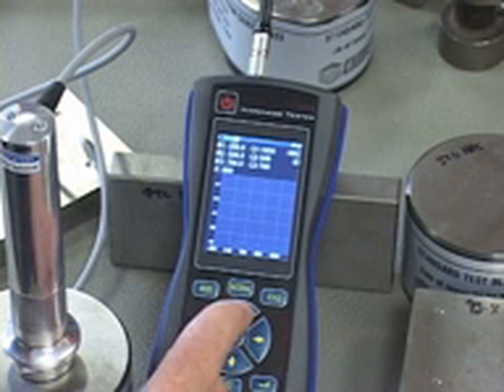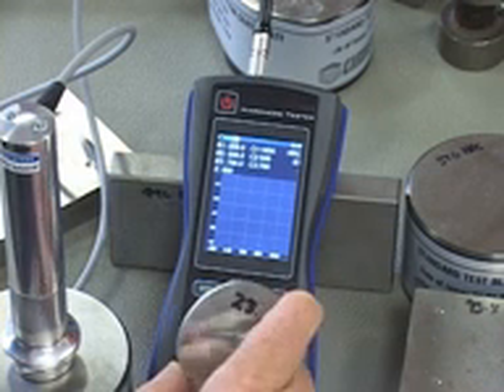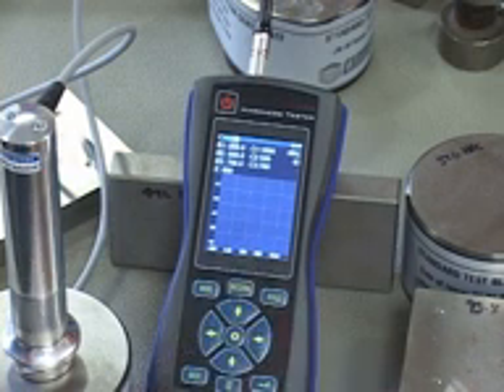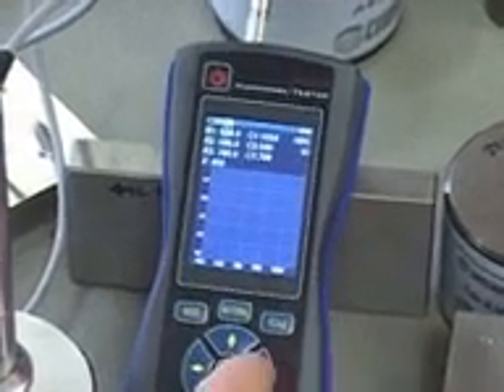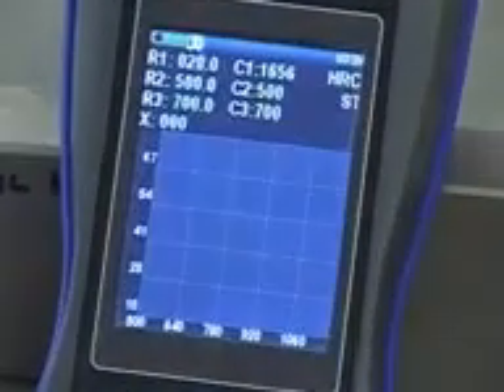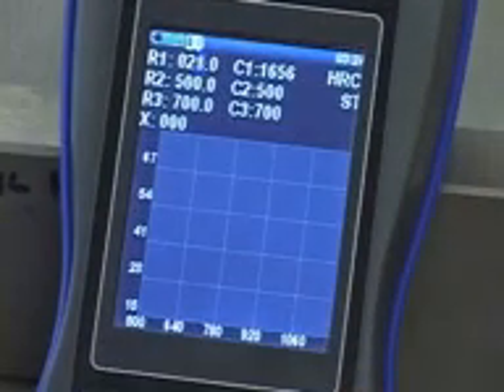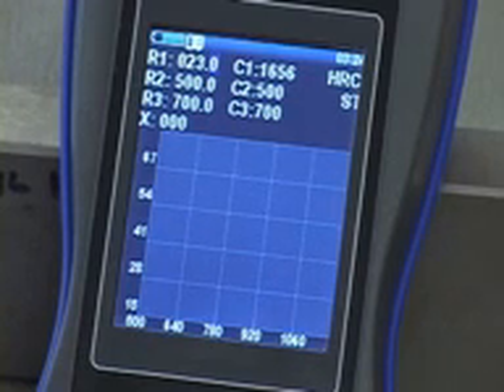So if I use the cursor control keys here, you can see I can scroll up and down to go to different values. So I want to make this 0 because this is a 23.17 test block. I then use the right cursor key and it moves the little blue box to the next value, and I use the cursor control key to change this to 2. Again, this is 23.17, this is going to be 3, and because we're working with 1 decimal place, we don't put in 17, we're going to round this up to 2, so it's going to be 0.2.